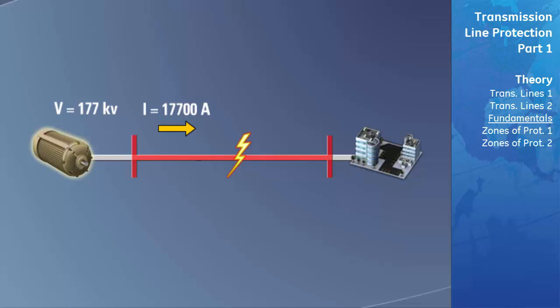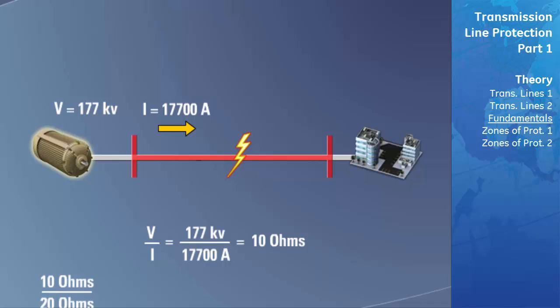By comparing the calculated impedance of the transmission line with the known impedance of the transmission line, you can determine how far along the transmission line the fault occurred, leading to the term distance or distance relaying. In this example, the current increased as a result of the reduction in impedance from 20 to 10 ohms, indicating that the fault occurred at a distance of 50 percent of the distance from the measurement point to the end of the transmission line.